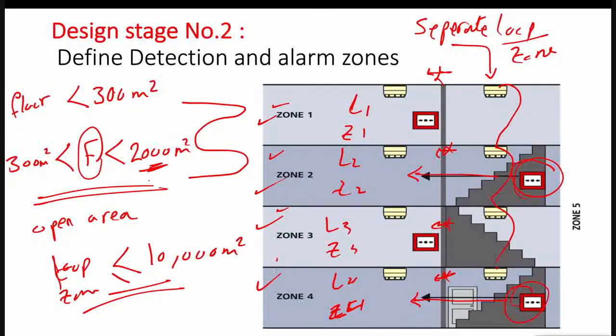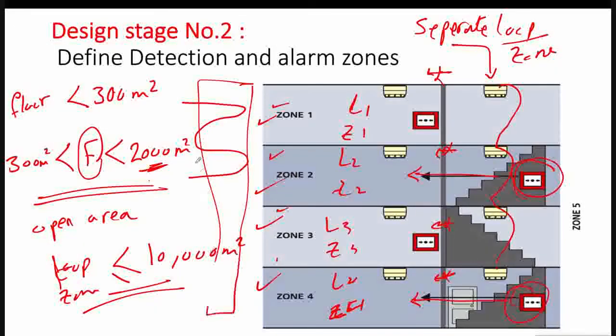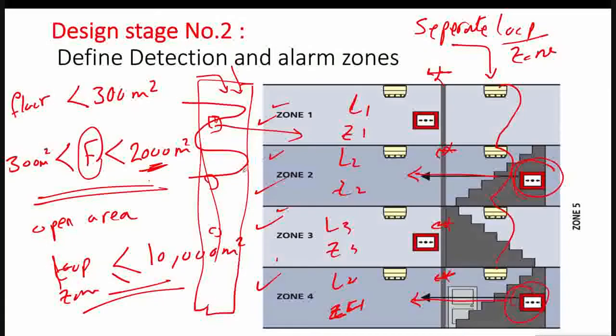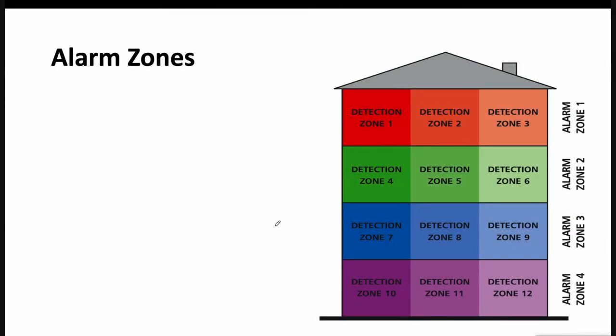Each floor should have its own zone, and all stairs should be on one loop. If there is another staircase, assign a separate zone or loop to it as well. All manual call points on that staircase shall also be connected to the floor zone.